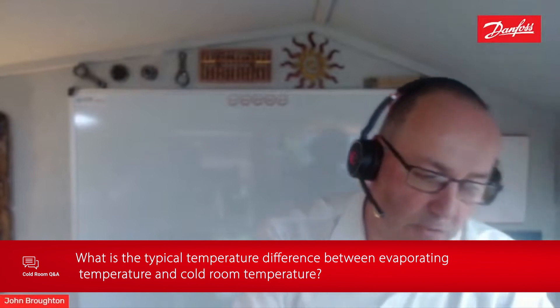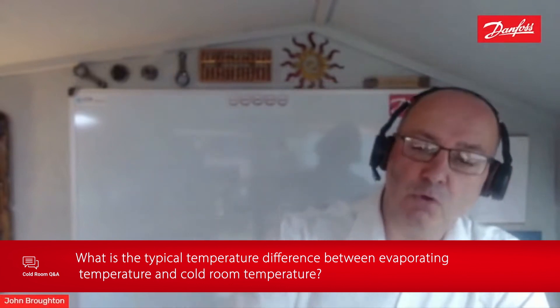Generally, if it's a frozen room, humidity doesn't matter as a sort of general statement. For temperatures at freezing and below, a 6K delta T is absolutely fine. And if we're talking about 6K delta T, you're looking at around 80-85% humidity. There's no point dragging too much moisture out of the air, because then you're just going to put that on your evaporators, and that's going to cost more money to defrost and block up your evaporators quicker.